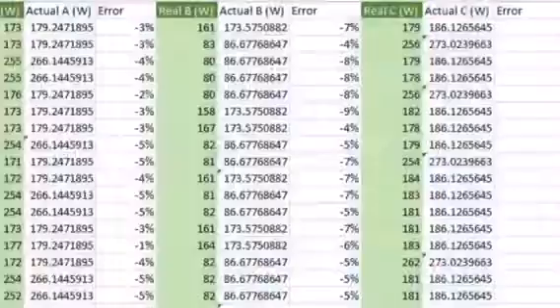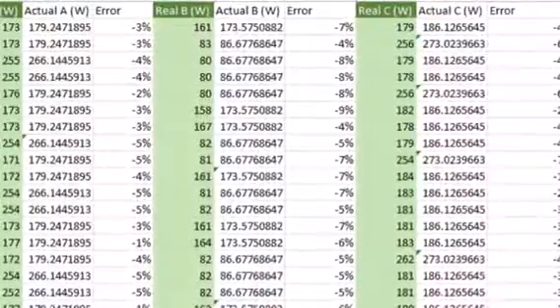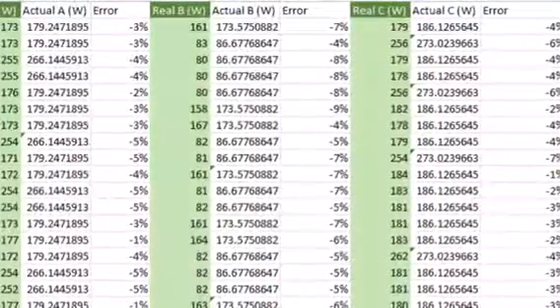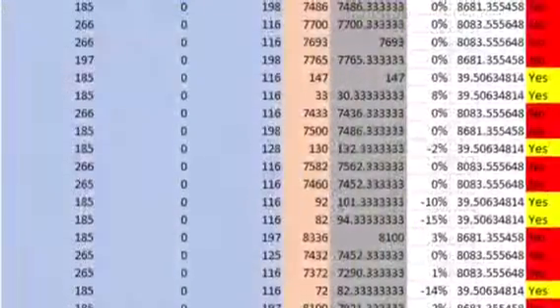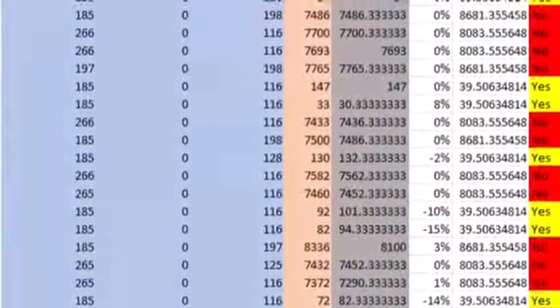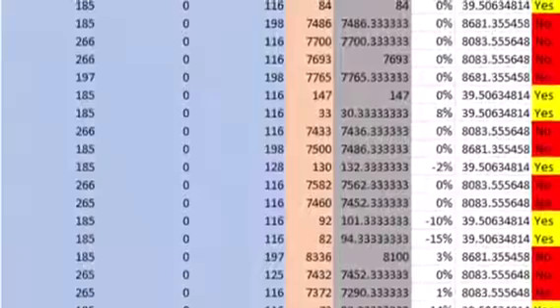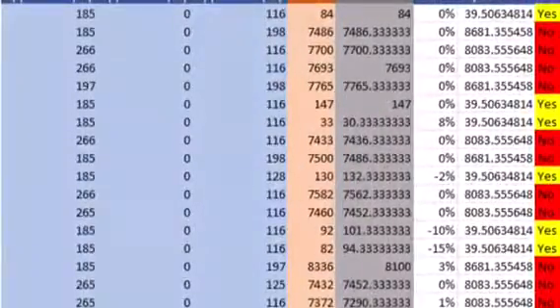By recording our data in Excel, it is possible to compare the predicted power measurements with the actual measurements for each state. The most balanced solution should then have the least variance across all 3 phases, or more generally, ensure that each phase is within 20% of the others by our definition of balanced.